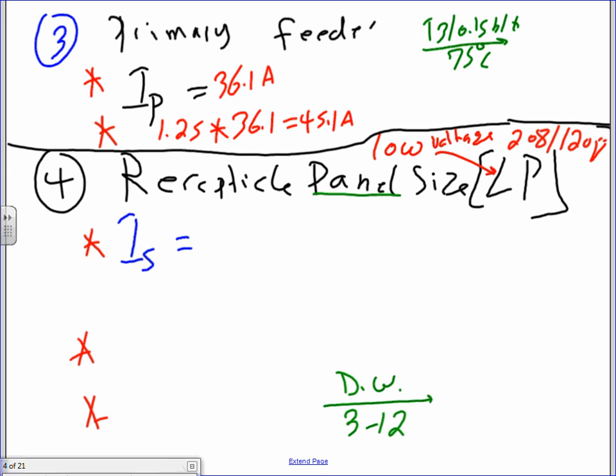From 45.1 amps, my friends, you're going to take it over here to 310.15(B)(16) and the 75-degree column. You're going to end up with three conductors, number 8 AWG. This is the size and the number of my conductors. Now remember, you go to the 75-degree column. So I have three conductors. Why three? Why not four? On the primary side, guys, there is no neutral. It's a delta, so we need only three conductors.